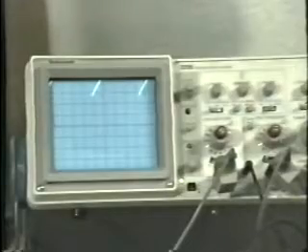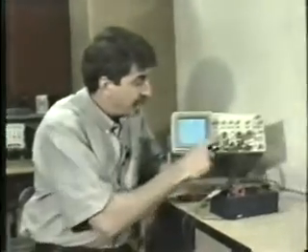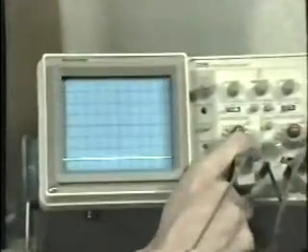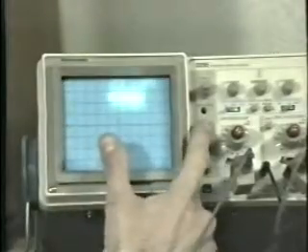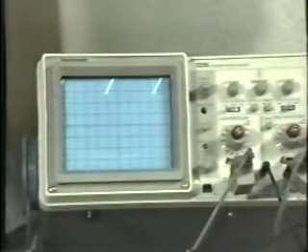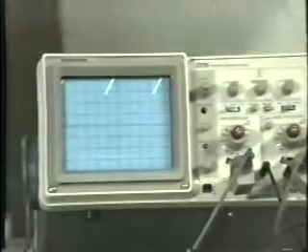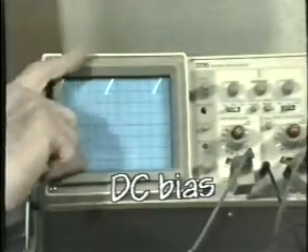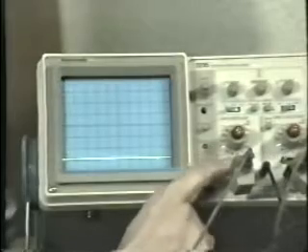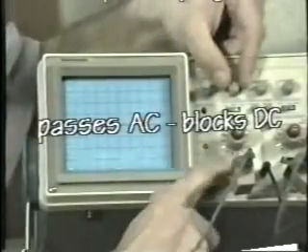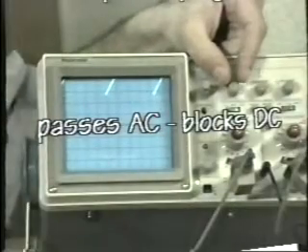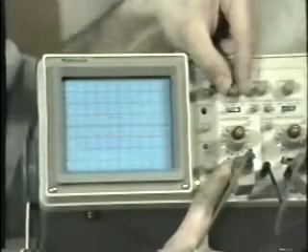Here's something else you may encounter: an AC signal that is riding on top of a DC signal. In this case, the waveform is partially off the screen. Setting the input select to ground shows the baseline down here, so whatever this signal is, it's way above the screen. The beam finder brings it down so you can see it's partially up there. This is not at all uncommon — to have some type of signal riding on top of what we call a DC bias. To eliminate that DC bias so you can see the signal, you flip the input select control to AC, which completely removes and ignores any DC on the signal.